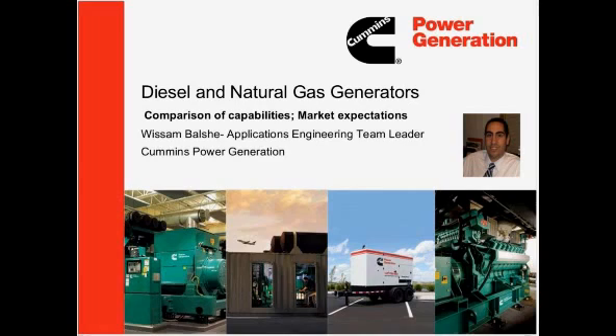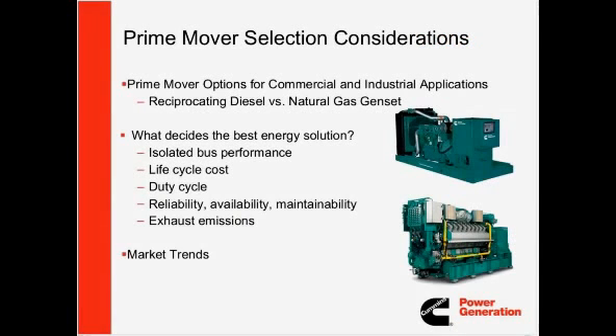So with that, we'll go into the selection considerations that go into selecting the fuel type for your prime mover. For industrial and commercial applications, we mainly use reciprocating internal combustion diesel and natural gas gensets. And there are a few factors that go into selecting that prime mover. Mainly, we're going to talk about isolated bus performance.